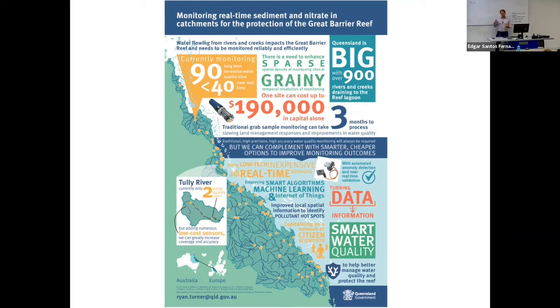Not only can this project help us design where the monitoring stations go and where we might adaptively change, it's helping us manage the data coming in by running algorithms, picking up the spikes, watching out when a probe is getting biofouled, watching out when a probe stops working and there are data gaps. And it's important that we manage that data because generally the public will see gaps and they'll think something else. Or they'll see a spike and they might accidentally go, oh, that's a huge lot of nitrate coming through, when actually it's an error from the probe.